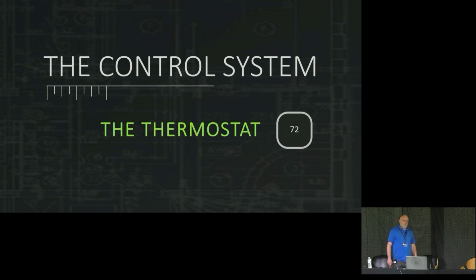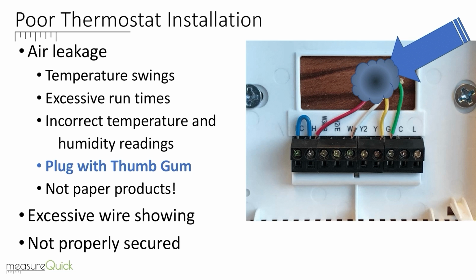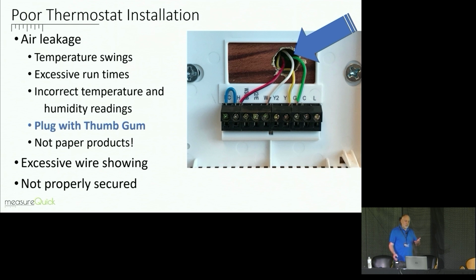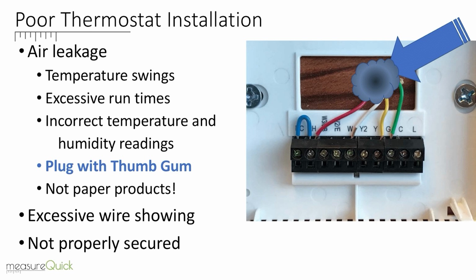There's a fellow here, that Ohio fellow, we were talking about this just last year, put in a new Bosch system. And one of the issues that we found was he had an unconditioned crawl space underneath the house, some supply duct leakage. The thermostat had a hole drilled for the wire to go up, obviously inside the wall. The supply duct leakage is pressurizing the crawl space, which is unconditioned crawl, sending air up behind the thermostat. And you put a brand new inverter system in, and the humidity is reading high on the inverter system. And it's reading high because we're pushing unconditioned air up behind the thermostat, and it's giving it a false high temperature, right?